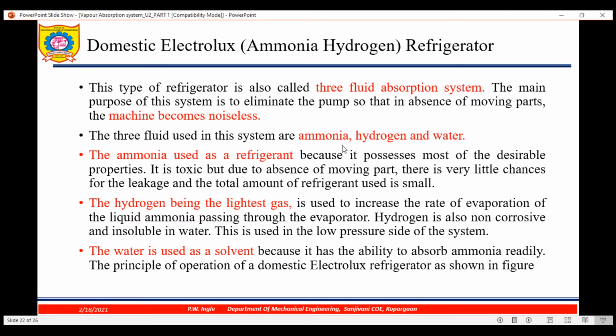Number one is ammonia, which acts as a refrigerant. Hydrogen is required to increase the rate of evaporation of liquid ammonia, and the last one is water. Water is used as a solvent. Again, I am repeating: ammonia is used as a refrigerant because it possesses most of the desirable properties. It is toxic, but due to the absence of moving parts, there is very little chance of leakage, and the total amount of refrigerant used is also small.